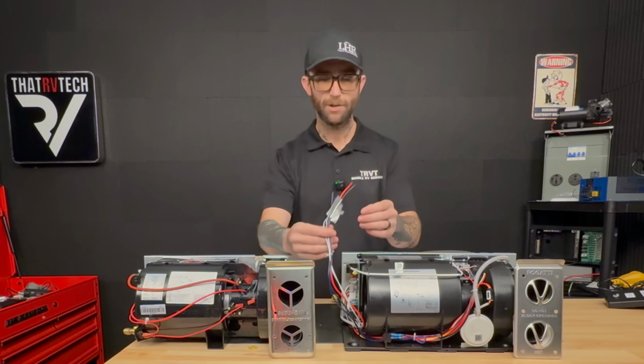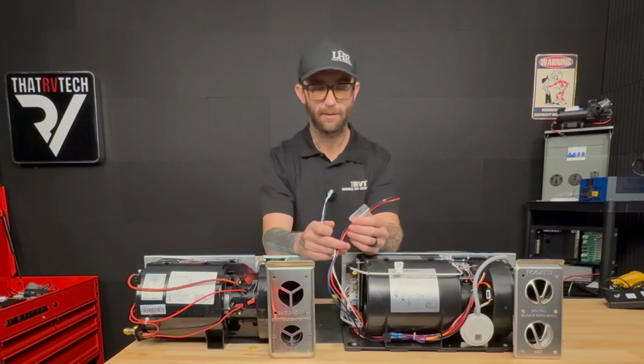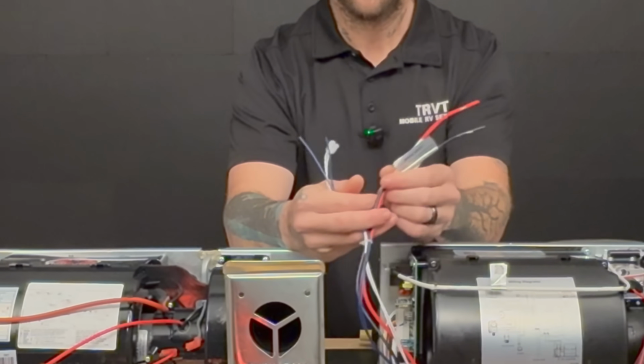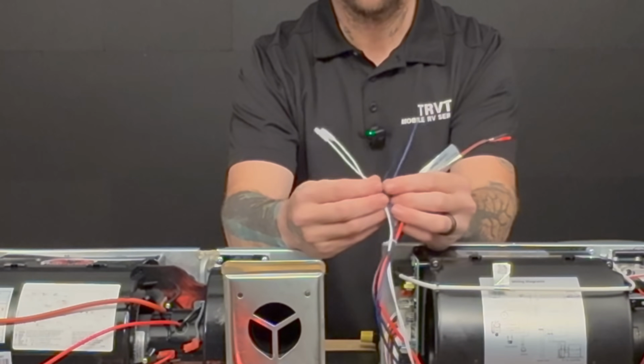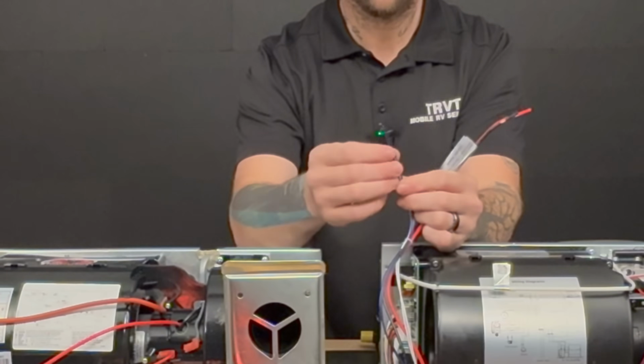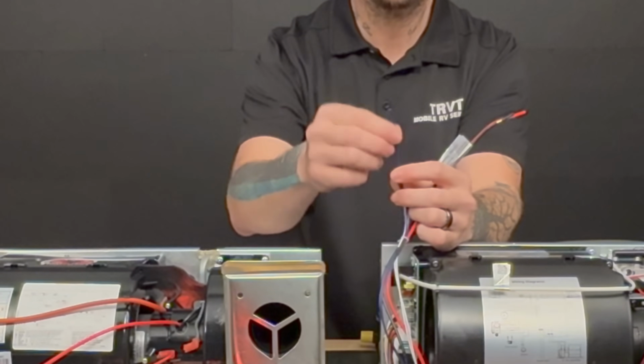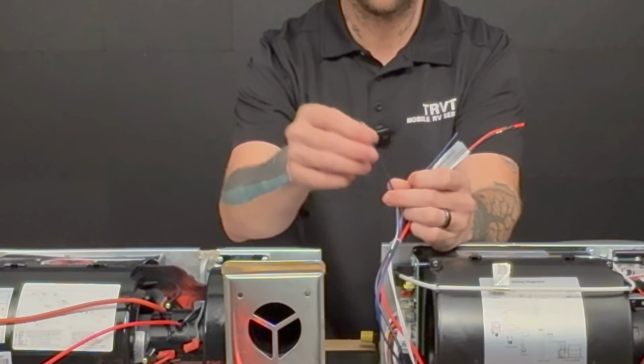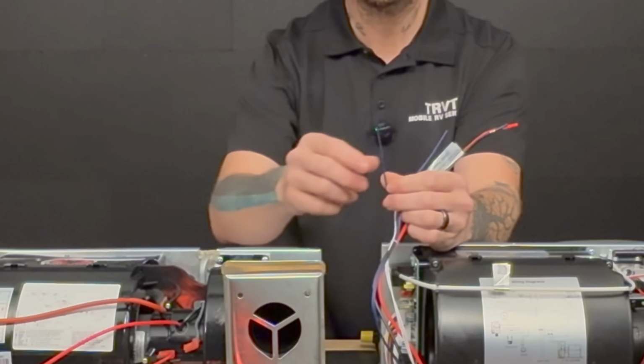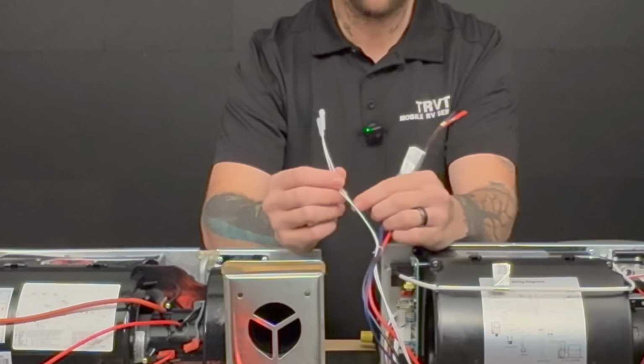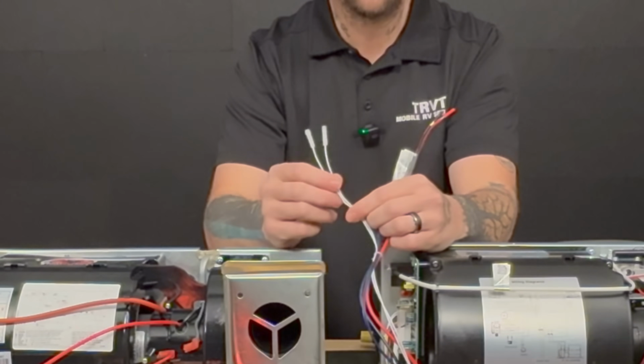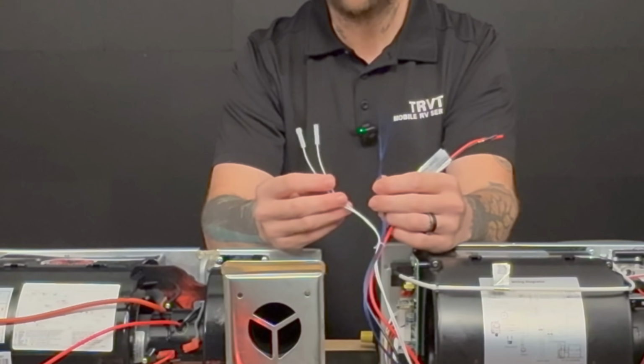On the wires here, just like most furnaces such as the Suburban, you'll have power and ground, and then two blue wires on a Suburban or Dometic for your thermostat loop. These two go to your thermostat, or a single wire if it's an in-command system. You also have two white wires that go to that controller I showed you, so you actually have options for both.